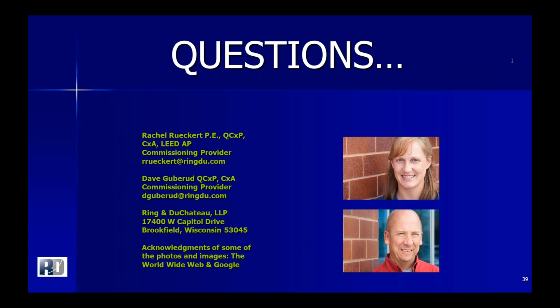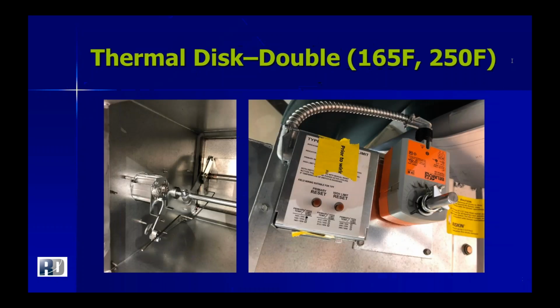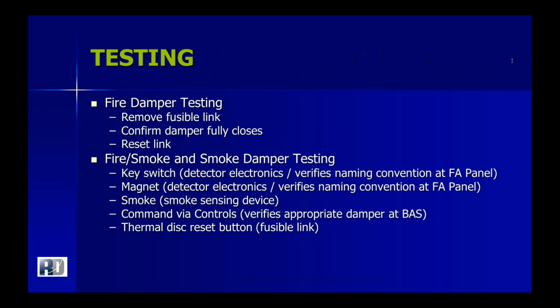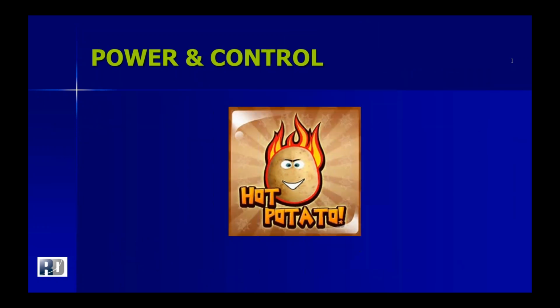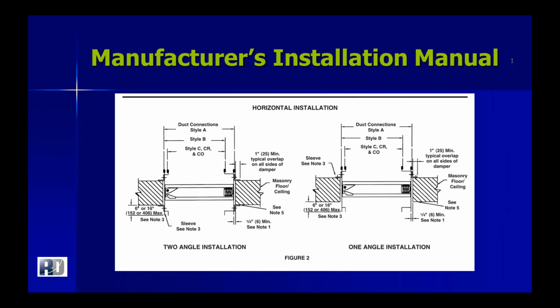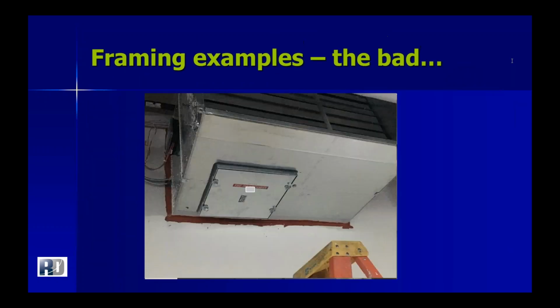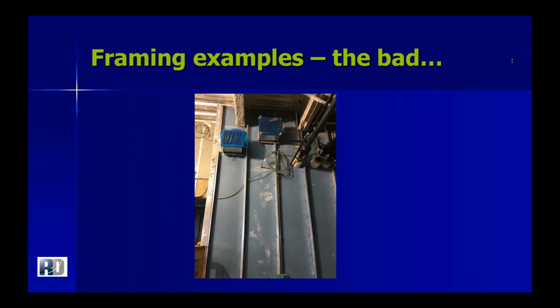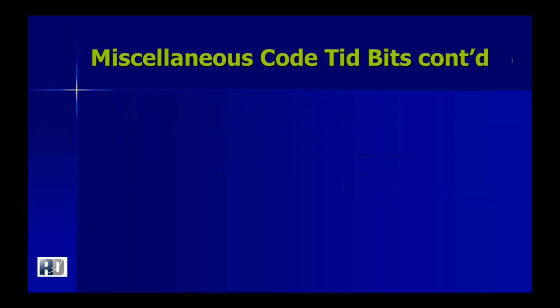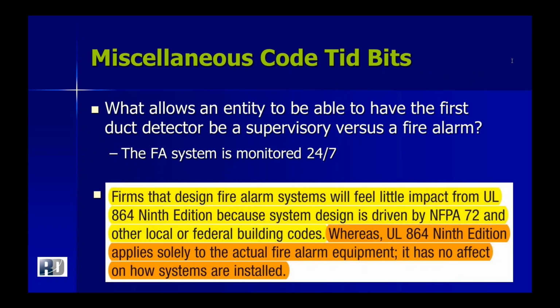Okay, I'll take the first swing at that one. Controls really are not controlling the fire smoke damper through the building automation system, and even our diagrams were trying to illustrate that really well. Everything's being done by electromechanical means and relays. Everything's hardwired connected. It's done by the control contractor doing the work, but it is not being operated through any building management system or controls, because you are absolutely correct. Johnson Controls has a product line that can be used as part of an engineered smoke control system, where many other systems do not have that capability.